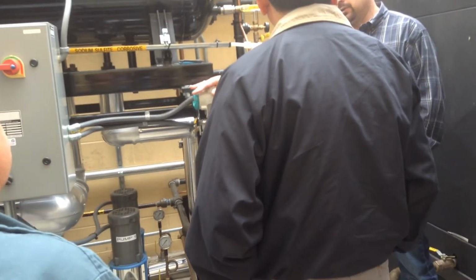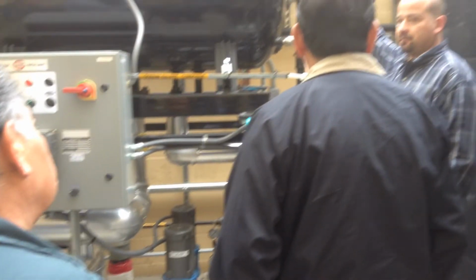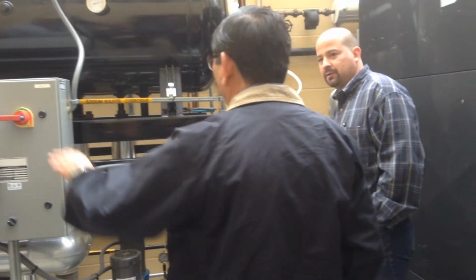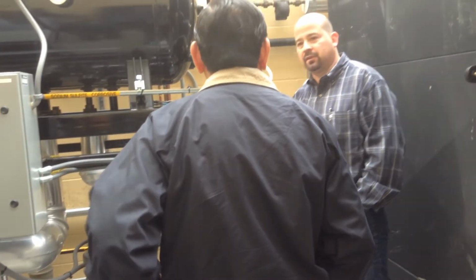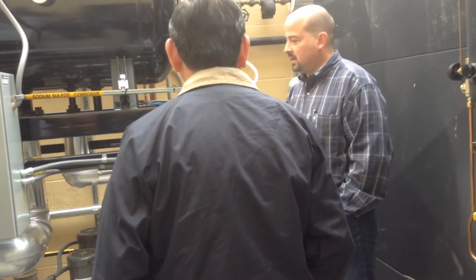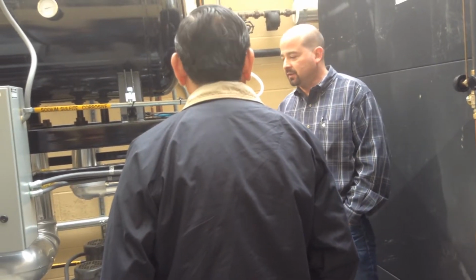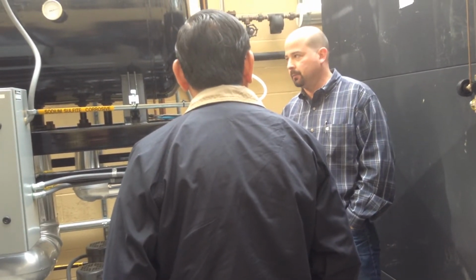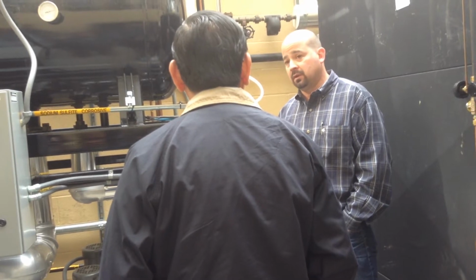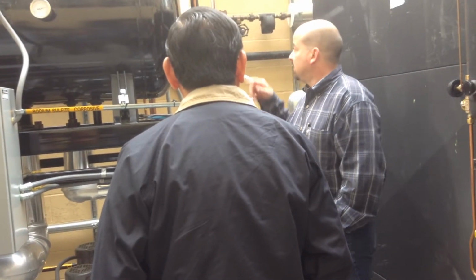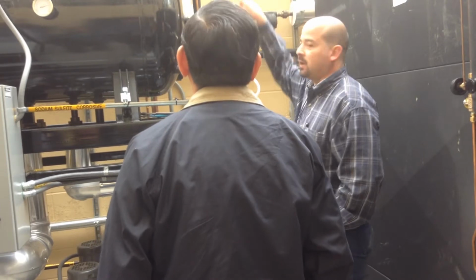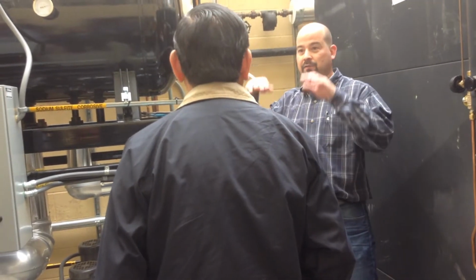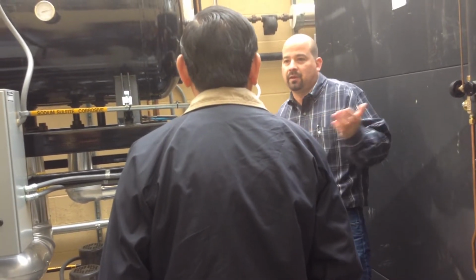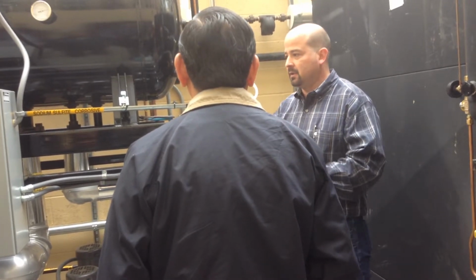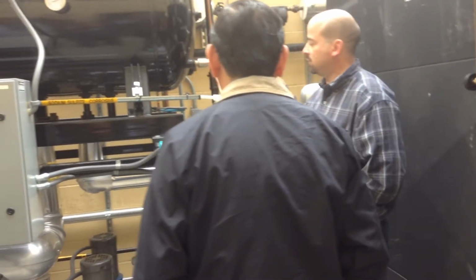It's a factory set point based on a measurement of inches of water column. So they'll take the level from here to down here. You don't ever have to touch it. The only time you ever have to touch it is, let's say you do preventative maintenance on this tank and you drain it. This line has to be primed because it's like a U-tube. If you lose the prime, it's not going to know if you have any water in there or not, and it's going to tell it what it shouldn't be telling. So it has to be primed.